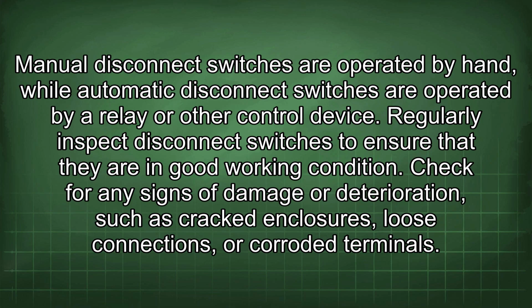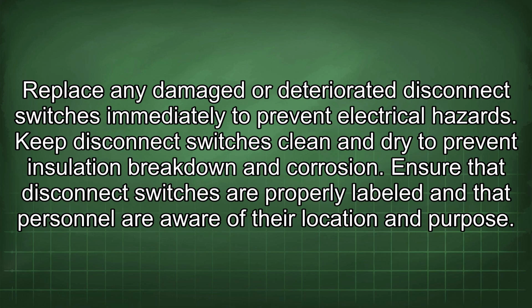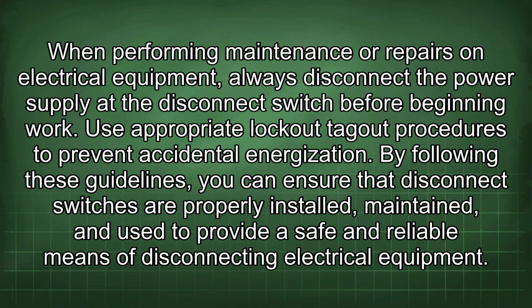Regularly inspect disconnect switches to ensure that they are in good working condition. Check for any signs of damage or deterioration, such as cracked enclosures, loose connections, or corroded terminals. Replace any damaged or deteriorated disconnect switches immediately to prevent electrical hazards. Keep disconnect switches clean and dry to prevent insulation breakdown and corrosion. Ensure that disconnect switches are properly labeled and that personnel are aware of their location and purpose. When performing maintenance or repairs on electrical equipment, always disconnect the power supply at the disconnect switch before beginning work. Use appropriate lockout-tagout procedures to prevent accidental energization.